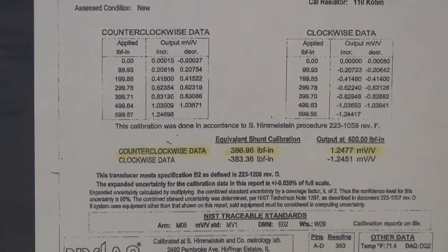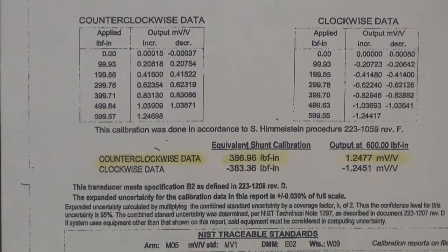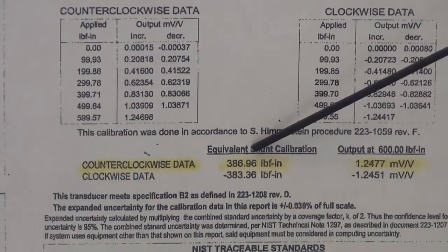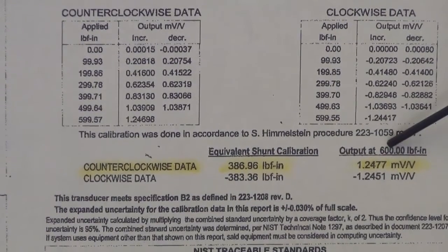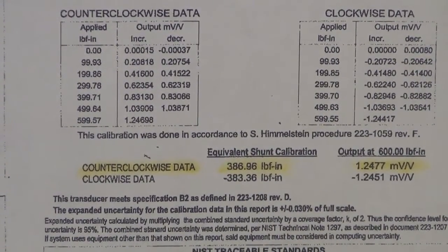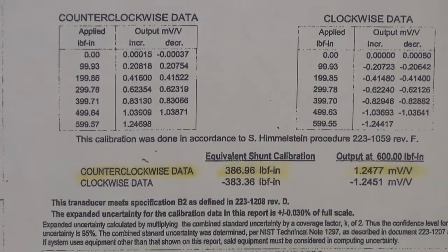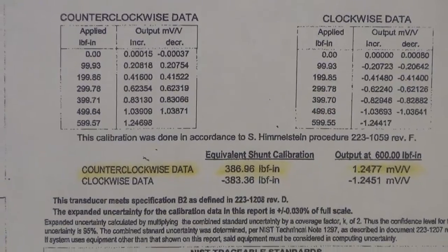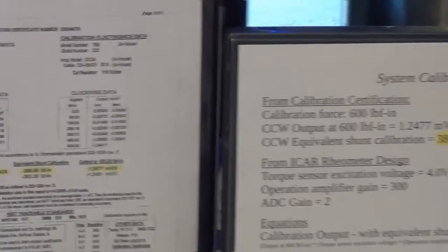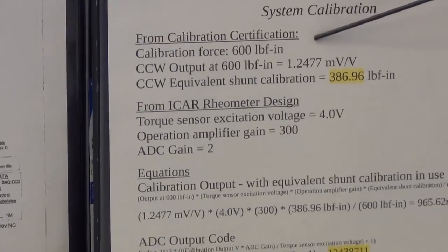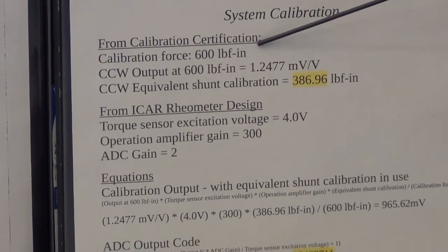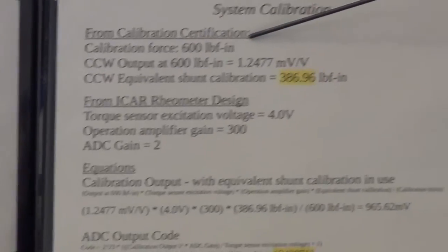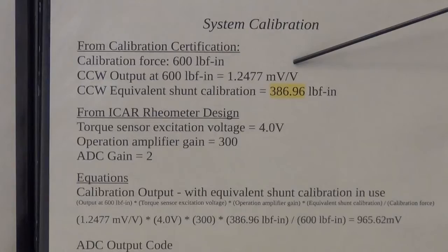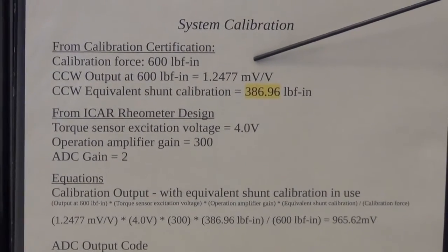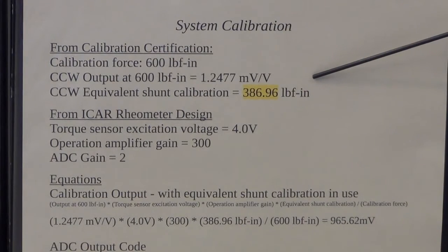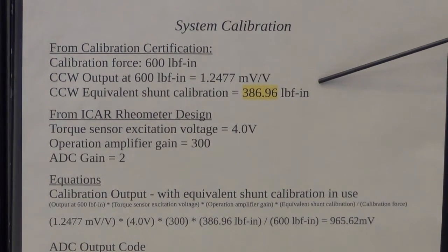Once you have the resistor in place, you need to grab two values off the calibration sheet. The equivalent shunt calibration and the output at 600 pound-inches of force for the counterclockwise data. Alright, once you have that, we can move to the second sheet. Again, this is the information that's coming from the calibration sheet. We know that we're using data that's for 600 pounds of force. We have the sensitivity at full scale, and we have the amount of force that the resistor represents.